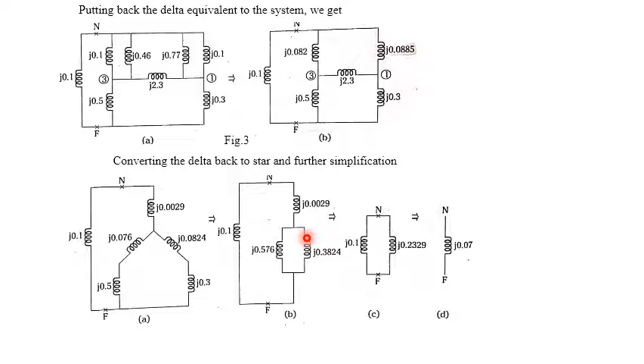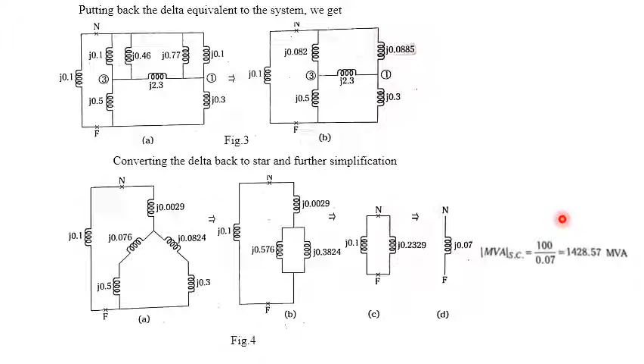What we have to calculate is the MVA short circuit. We know it is on a 100 MVA base. The Z per unit we got is 0.07. Hence we get the MVA short circuit as 1428.57 MVA. This is how we solve the problem on a 100 MVA base.